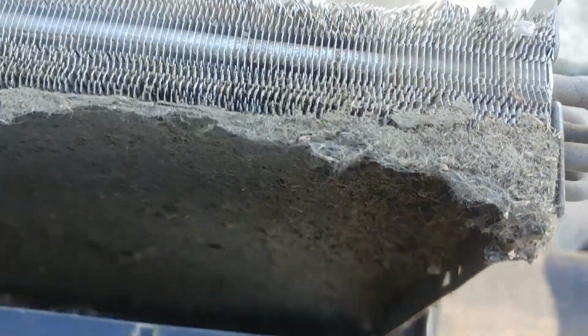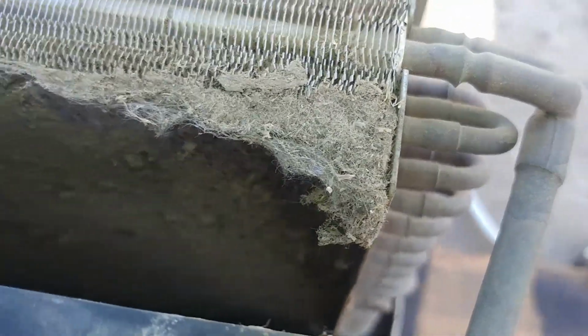Alright, so here's the state of the coil inside of this room air conditioner. As you can see, there's a tiny bit of airflow that could go through right there, where the fan pushes a very minimal amount of air. So I'd say this coil is like, I don't know, 90% blocked. It's probably 10 to 15% remaining that's not blocked.